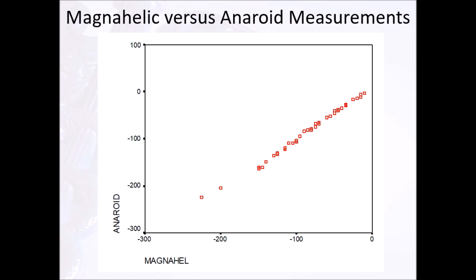What I've shown here in this slide is the setup of the same type of device that was shown for the most part for testing in slide number 34. You can take a sphygmomanometer pressure gauge, just take the rubber tubing off, take this particular setup that I described earlier in slide 34, attach the oxygen tubing with it to this particular part of the sphygmomanometer, and the mouthpiece would be here, from which you could hopefully obtain in a single patient a maximal inspiratory and expiratory pressure.